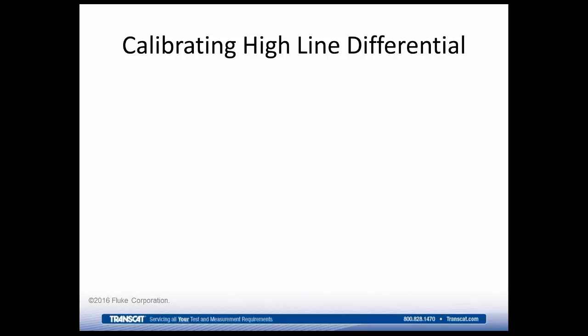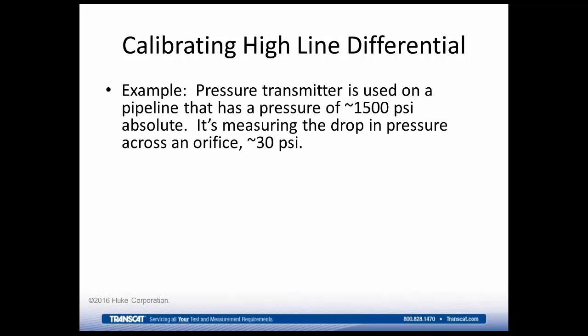A very big challenge is calibrating something at a high line differential. Once again, what we mean by that is where the line pressure, the starting point, is a very high pressure. And then we're measuring the test pressure as being slightly different from that line pressure. So the example here is a pressure transmitter used on a pipeline, and so that pipeline has a pressure of about 1500 psi absolute. And it's measuring the drop in pressure across an orifice. And that drop in pressure is about 30 psi. That would be 30 psi differential.